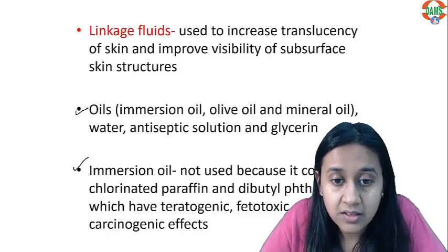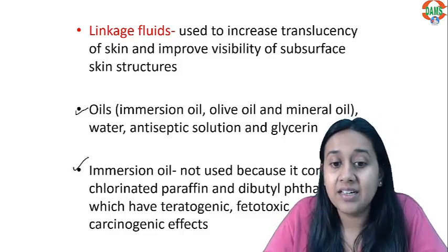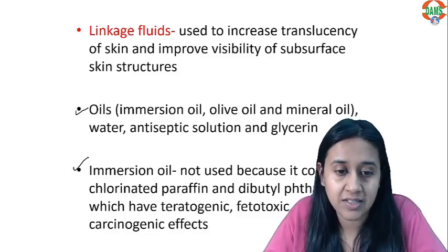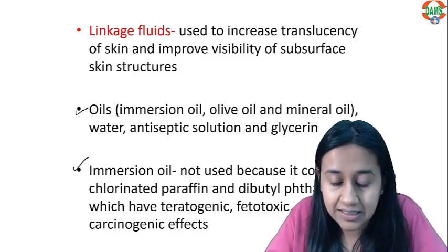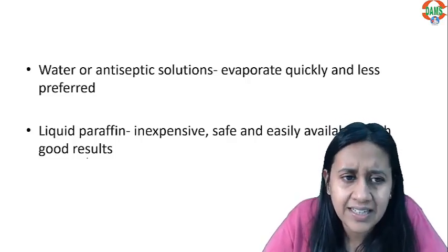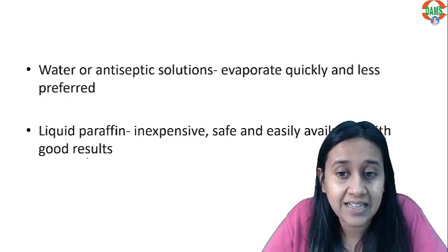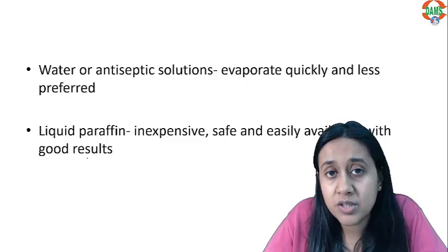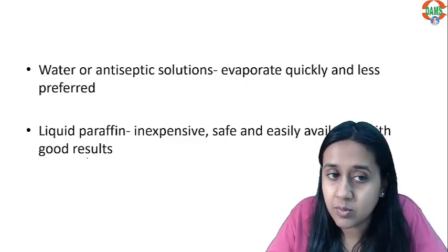The immersion oil is not used because it contains chlorinated paraffin. It contains dibutyl phthalate, which has teratogenic, fetotoxic, and carcinogenic effects. So if you're using this on the skin, that would not be a good practice. Water or antiseptic solutions evaporate quickly and they are less preferred. Liquid paraffin is inexpensive, safe and easily available with good results, and that is why in most dermoscopes, the linkage fluid which is used is actually liquid paraffin.